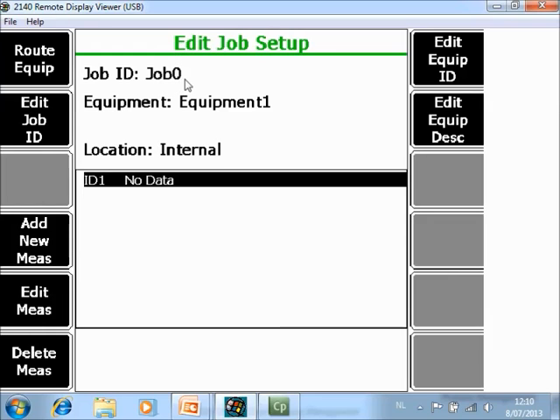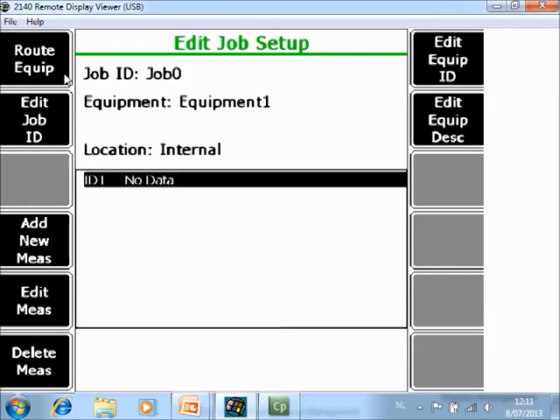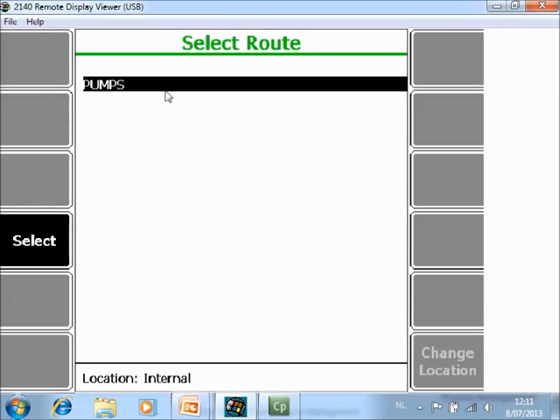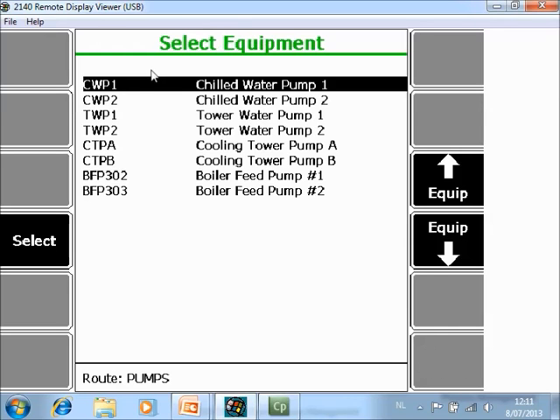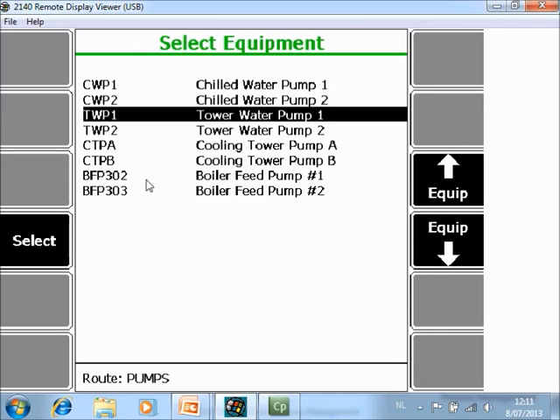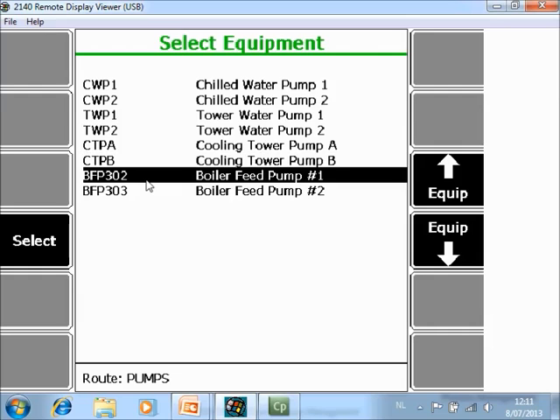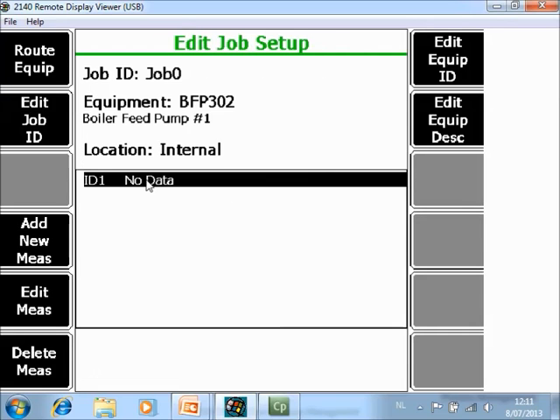Alternatively, if you have routes in the Analyzer, you can also recall an ID name of a route equipment. So push F1. Then you see a list of all the routes. In this case only one. Select the route. And here you see all the names of the machine. So if I now select, for example, boiler feed pump number 1, this will be immediately inside the route.